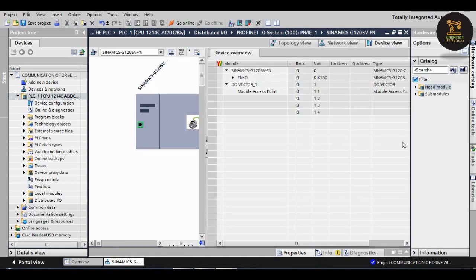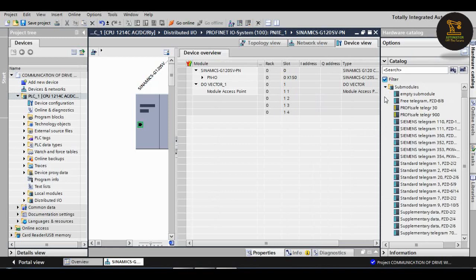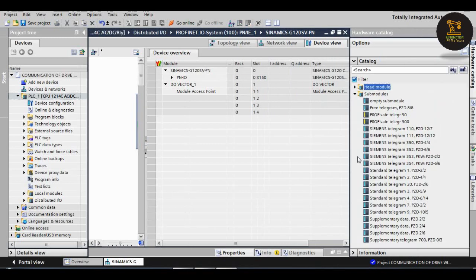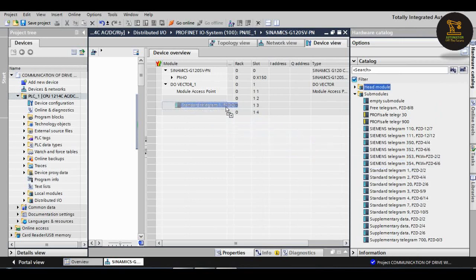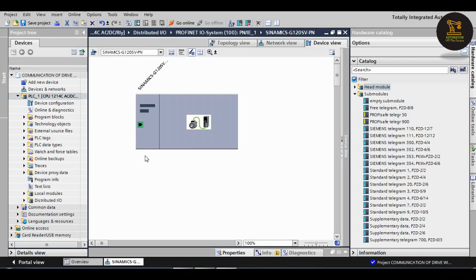Next, double click on the drive. When the drive appears, open the device overview. Then we should add the telegram, standard telegram. It is there in the sub modules. In that, standard telegram PZD 2 by 2, drag and drop there. The output is QW 64 and 67. Input is 68 and 71. We should remember the outputs.